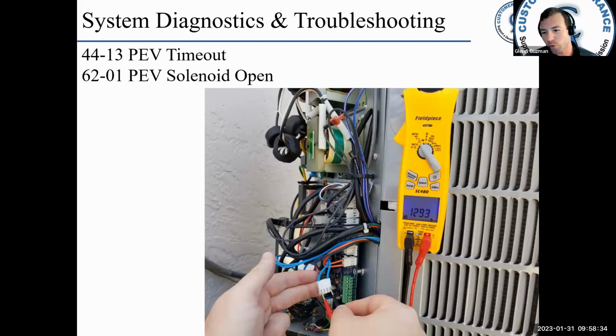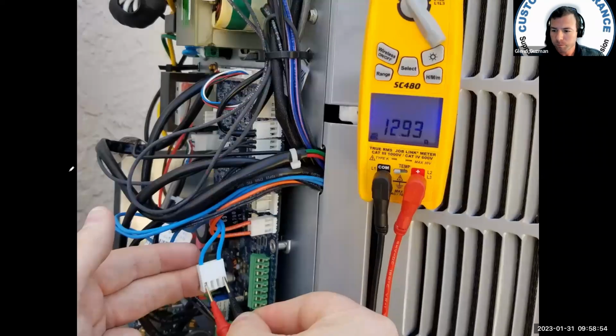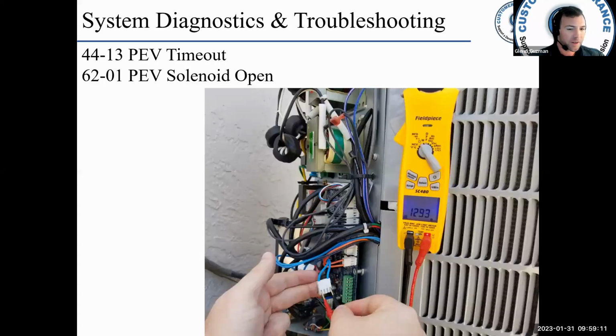6201 is a PEV solenoid open. That's pretty easy, right? The solenoid is open. Is it really? Okay, let me ohm the solenoid. I'm going to zoom in here so you can see I have 2 meter leads on the plug. That's my pressure equalizing valve wires there, 12.93 ohms. That's not K ohms, that's just ohms. So give or take 13 ohms, right?